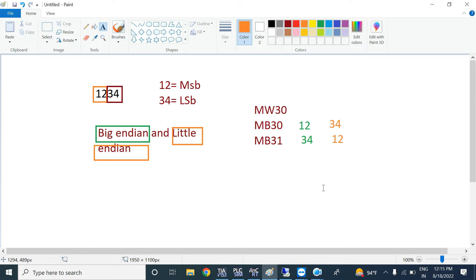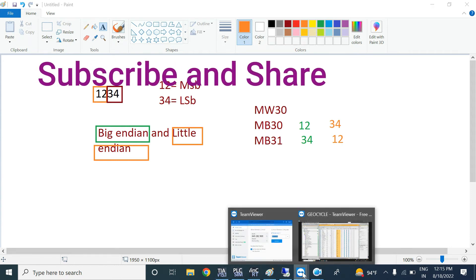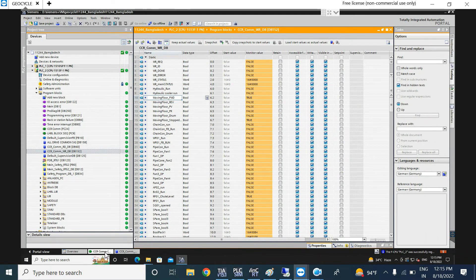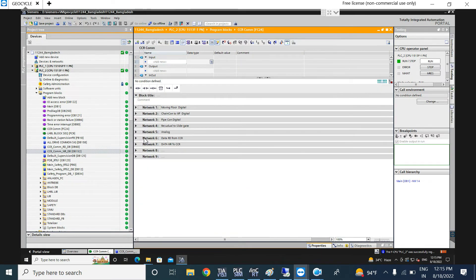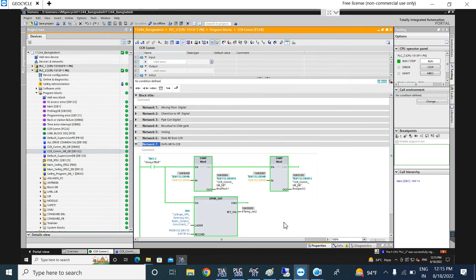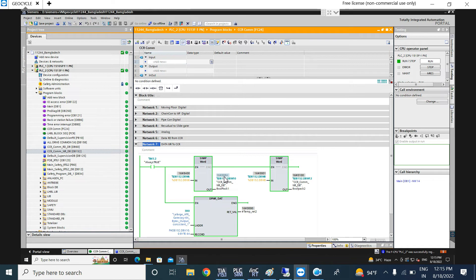We already use swapping in our existing plant. Looking at the instruction we already use here — this is a word swapping instruction. That word has two bytes: one byte is 84 and the other byte is 00. So after swapping it will become 00 and 84. Now let's look at why swapping is needed.